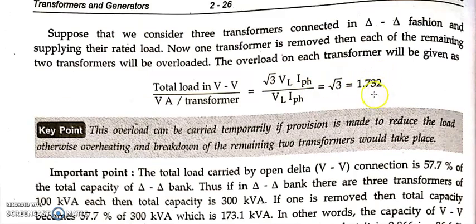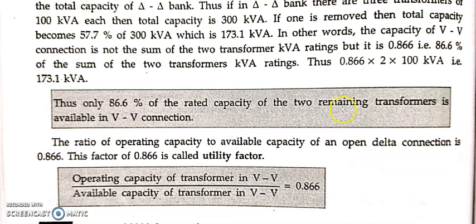So to avoid that, what you can do is reduce the load. As per our calculation, you can put it to 57.7%. There are two ways of remembering this 57.7%, that is the available kVA. How is that? It is 57.7% of the total kVA of the transformer. Here they have assumed each transformer has a rating of 100 kVA. So all three transformers together will have a rating of 300 kVA. That's why they are multiplying 57.7% of 300 kVA, which results in 173.1 kVA. This is one method.